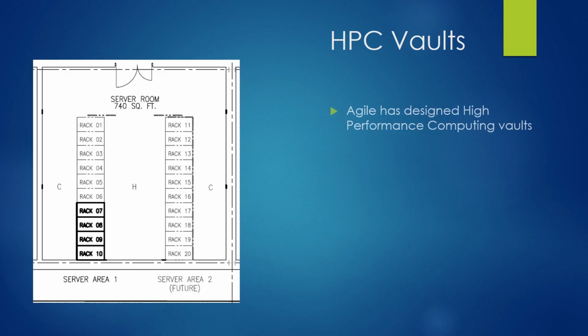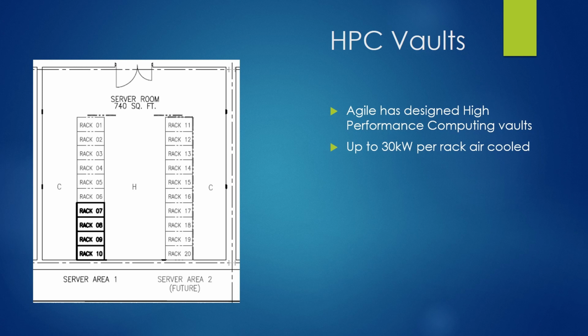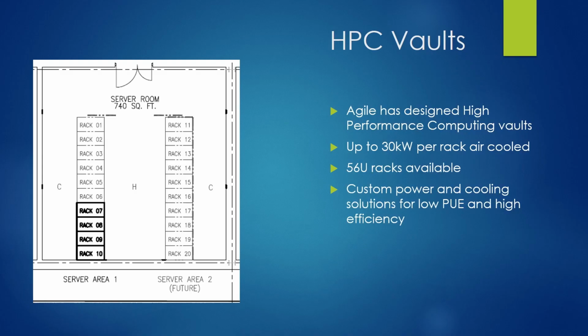Agile Data Sites, for example, has designed high-performance computing vaults — small rooms made specifically for HPC, designed for up to 30 kW per rack of air-cooled power. One way we do that is with very tall 56U racks, so we can fit as much as possible into this small space and keep the distance between computers close. We provide custom power and cooling solutions for low PUE, so they're very efficient.